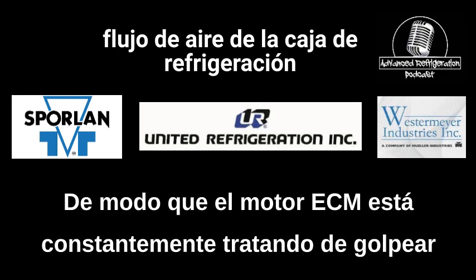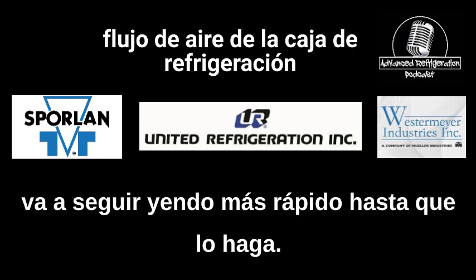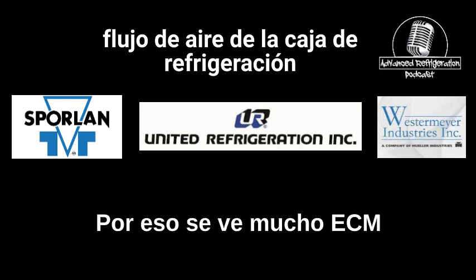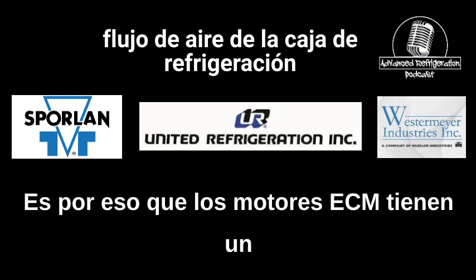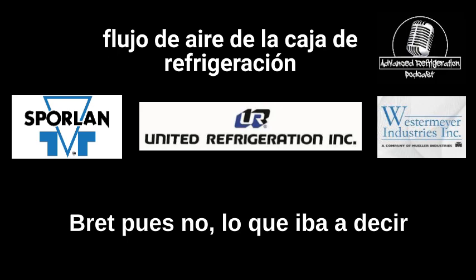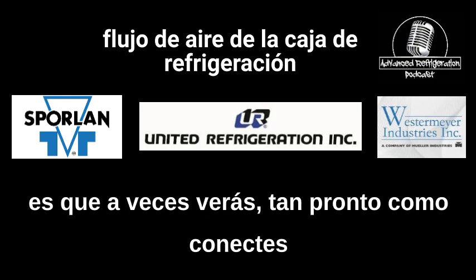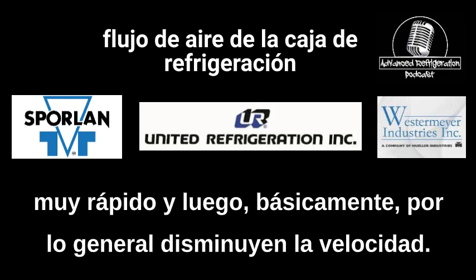So that ECM motor is constantly trying to hit a target. And if it's not hitting it, it's going to keep going faster until it does. That's why you see a lot of ECM motor failures early on. That's why ECM motors got a bad rap. Well, no, what I was going to say is, sometimes as soon as you plug them in, they'll start up and start spinning really fast, and then they usually slow down.